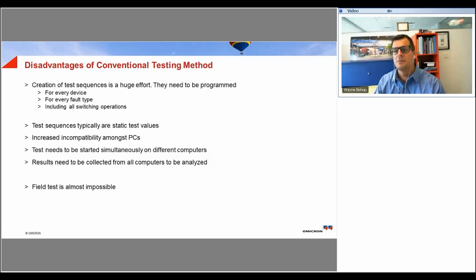We found that introducing additional components into the test setup not only increases the complexity of the test, but also increases the chances that PC software versions and firmware versions might not be compatible with local hardware. So with any kind of increase of assets, you're always going to run into an increase of compatibility issues. Another issue could be that the coordination between test engineers and technicians of when to begin the test can be very troublesome, and it can provide technical issues. And then lastly, after the test, additional time must be spent comparing timestamps from each of the test results from each of the test devices, matching them up, and making sure that they all align accordingly.